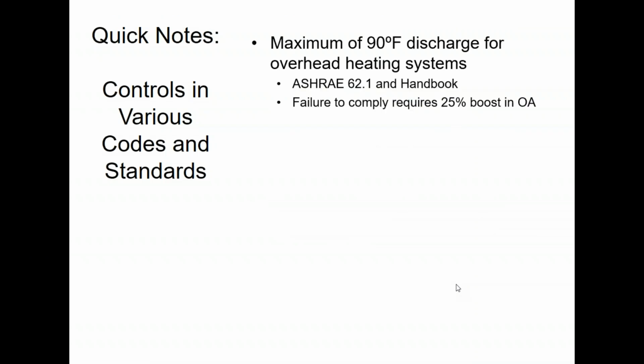All right, a couple other things, just quick bullet points as we wrap up on our last slide here. And we do have one more quiz question as well. ASHRAE 62.1 and the ASHRAE handbook both specify a maximum for overhead heating systems. So think of an office building with a rooftop, if you will. Overhead heating systems, no more than 15 degrees supply air above the space temperature. So if the space temperature was 75 degrees, your maximum heating supply temperature is 90.